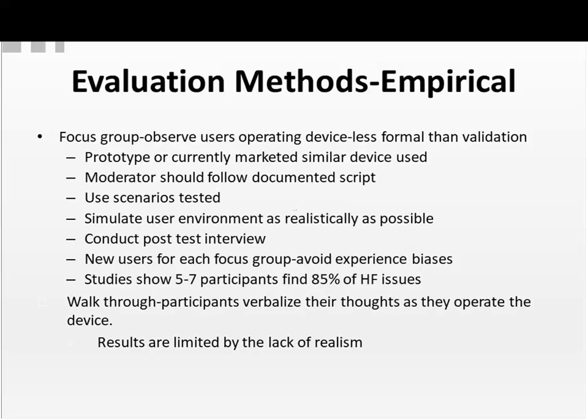You should have a moderator. You should follow a documented script, so he always does the same thing to the same people. You test the use scenarios. You should simulate the user environment as realistically as possible. You conduct a post-test interview following the test of each participant.